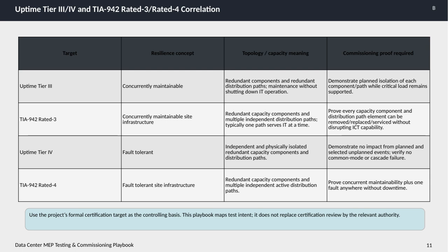This requires independent and physically isolated redundant components and distribution paths, ensuring that the system can handle planned and unplanned faults with no impact on IT operations. Commissioning must verify no common mode or cascading failures occur. Similarly, TIA 942 rated 4 represents fault-tolerant site infrastructure with redundant capacity components and multiple active distribution paths. Commissioning demands proving concurrent maintainability plus the ability to tolerate a fault anywhere without downtime.